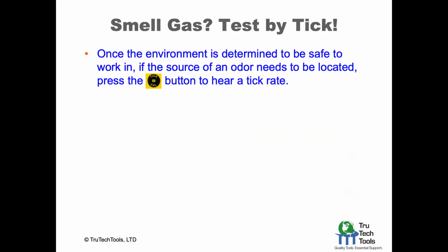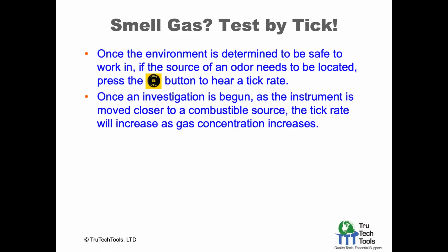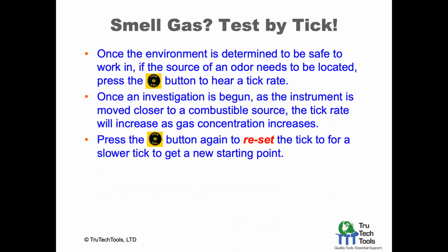If you smell gas, you can test by using the tick rate, the increasing tick rate. If your environment is well below the lower explosive limit, you haven't even switched over on the screen, and you want to locate the source of the odor, so you're locating a fuel leak, press the tick button, which has the B on it. Just tap the tick button and you'll start hearing the tick rate. As you move closer to the combustible source and the concentration increases, the tick rate will increase. And if you find that the tick rate is just going crazy, that means you've saturated the instrument at that point.